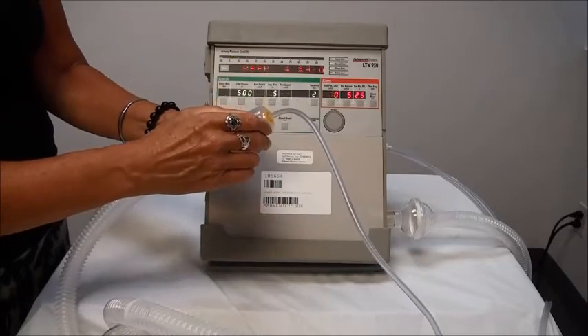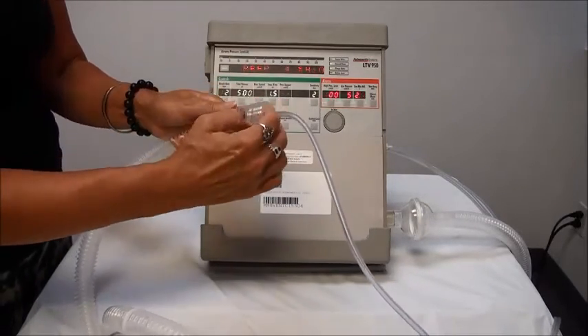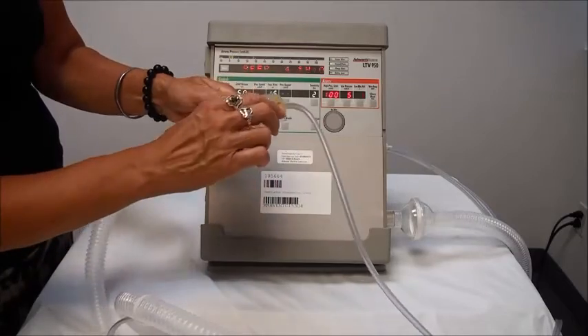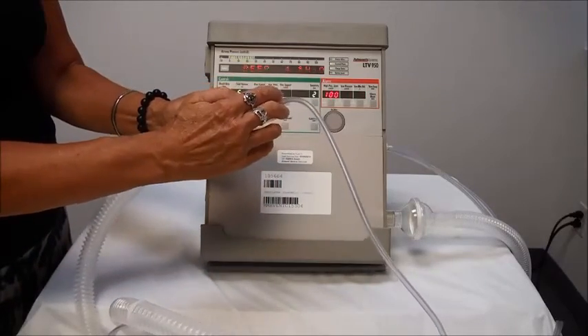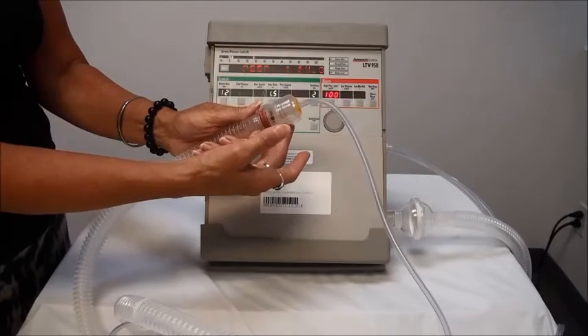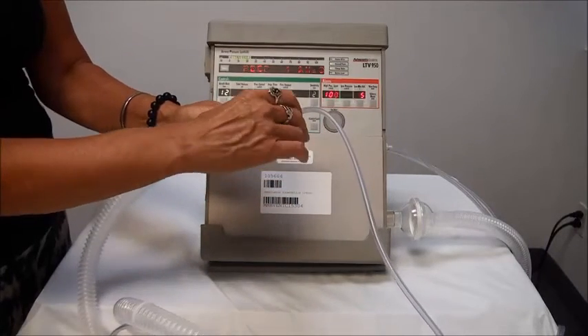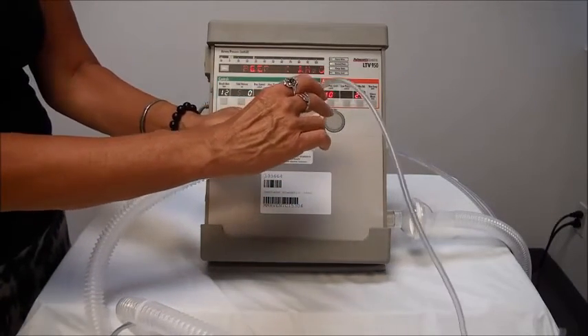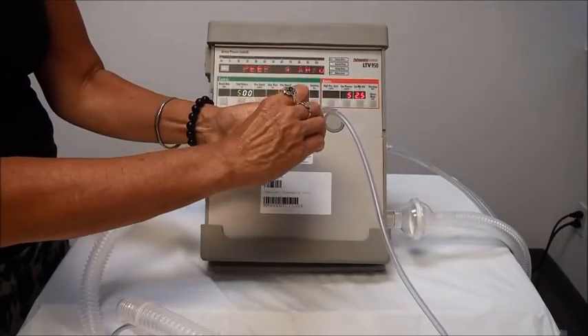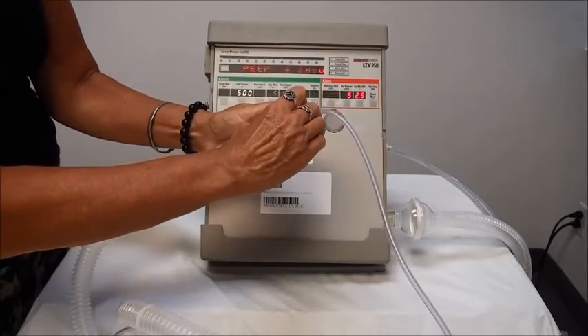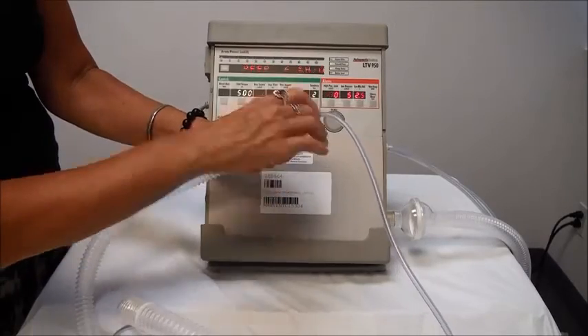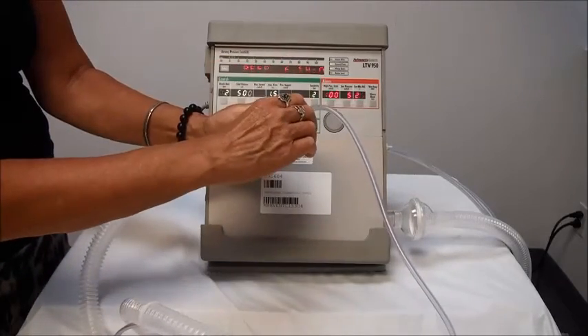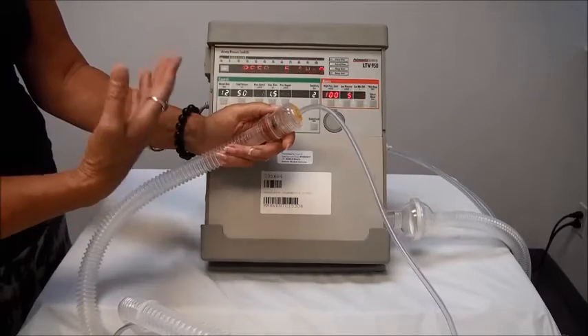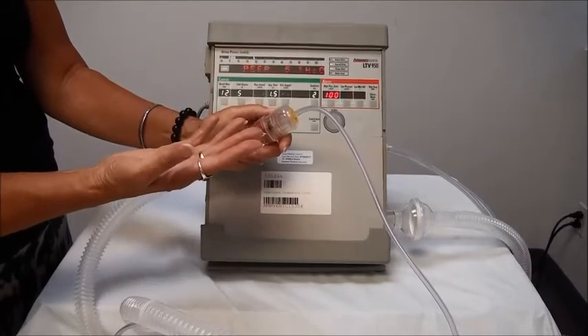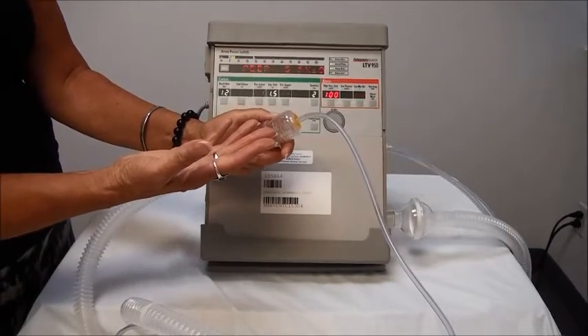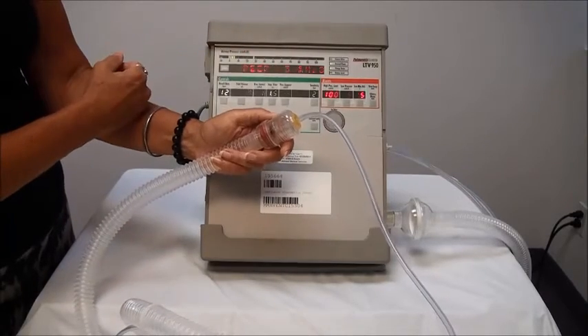So what I'm going to do to set this is, there's a little yellow disc on the top, and you need to push down on that to twist your PEEP valve to set it where it needs to go. Now I'm going to push down on this and twist. As I'm twisting this valve clockwise, my PEEP is going to go up. So I want to set it, and I want to wait a couple breaths because it can take a couple breaths to maintain where it needs to be. So right now I have it set at 5.